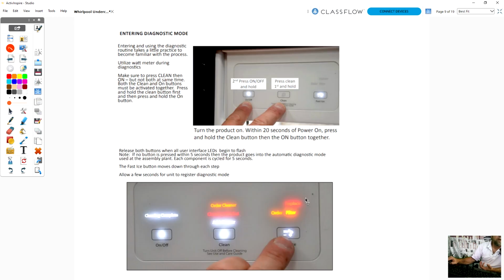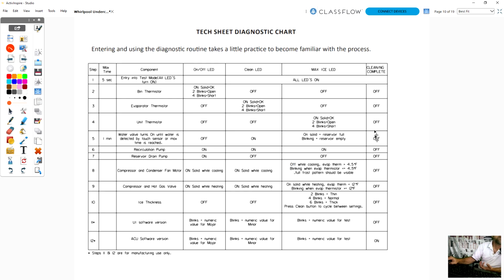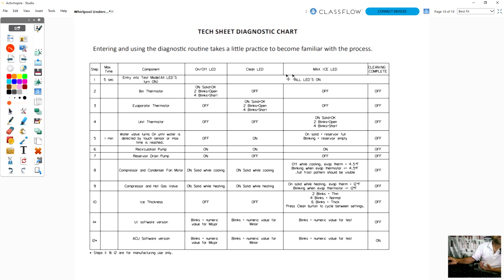So when you look here, one of these lights is going to say max ice. It might be underneath where his finger says, I don't know, it says fast ice. That might be what they're calling max ice. So that LED would be on. The clean LED is off, and this is off when we're checking the ice thickness. So you have to see what lights are on and what lights are off to know what step you are in.